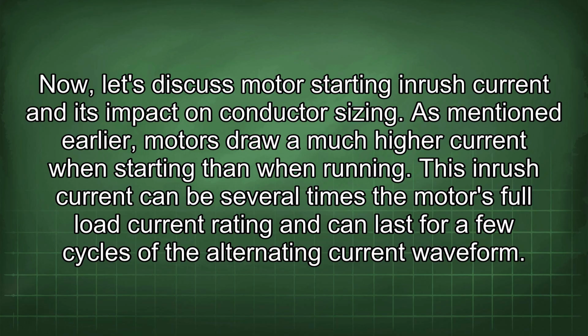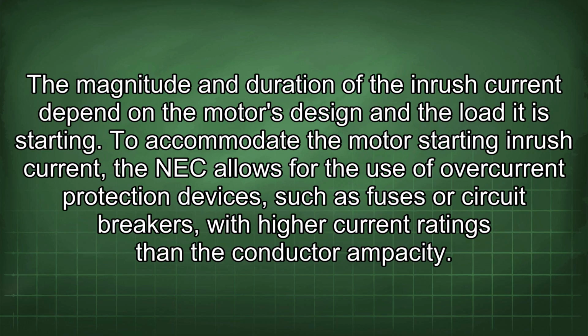Now, let's discuss motor starting inrush current and its impact on conductor sizing. As mentioned earlier, motors draw a much higher current when starting than when running. This inrush current can be several times the motor's full load current rating and can last for a few cycles of the alternating current waveform. The magnitude and duration of the inrush current depend on the motor's design and the load it is starting.